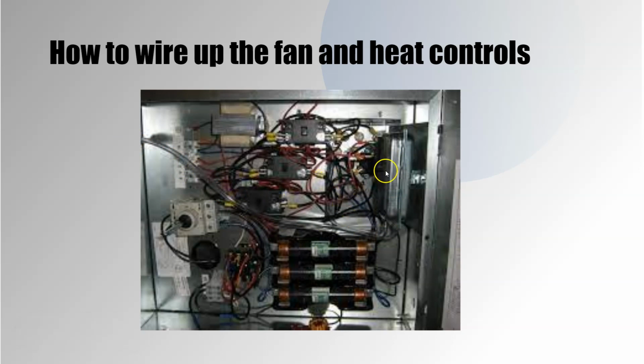So if you have 24 volts going to it and it's not turning on, this is the first place you have to look: is the air proving switch made? If you have 24 volts going into it but not coming out of it, then either you have a faulty air proving switch or you're not getting enough air volume through your VAV to close the switch. That's a problem a lot of the time. So you'll have to open up more air to the room during heating mode. That way you could close your air proving switch and turn on your heat. The next one is stage 2 heating, and the next one is stage 3 heating.